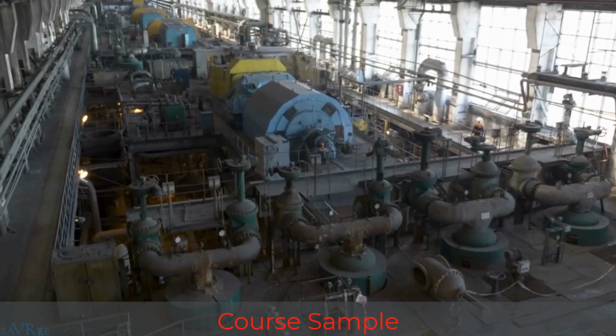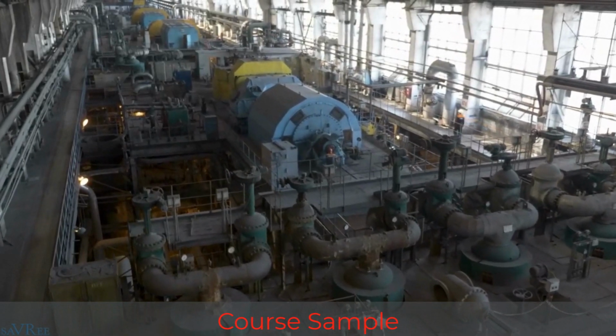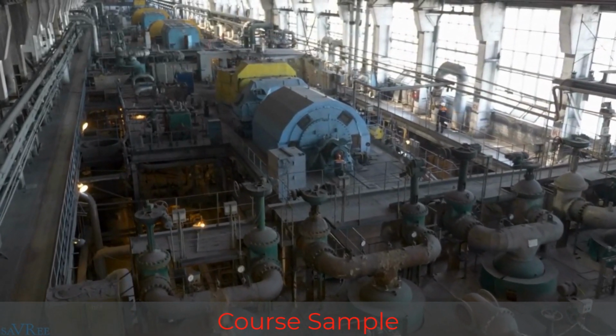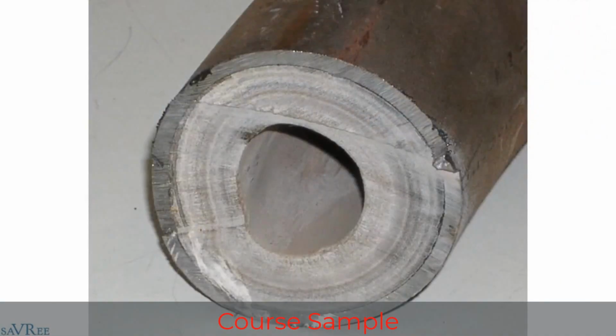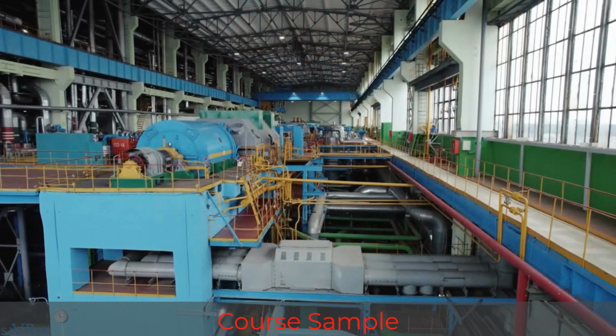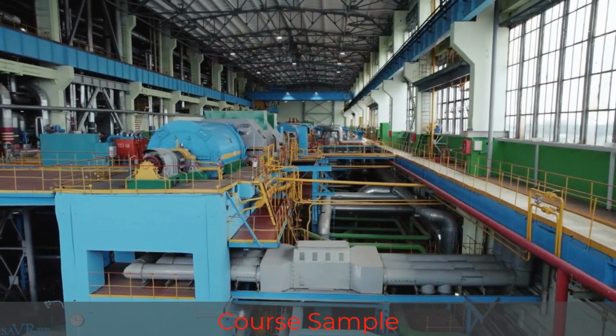processes, water carryover to our other heating surfaces such as the superheaters, and this may lead to things like scale developing on the inside of our heat transfer surfaces such as inside the tubing, and this again will reduce the heat transfer rate for our tubes, which gives us an uneven thermal distribution across our heat transfer surfaces and increases the likelihood that we damage our boiler tubes.